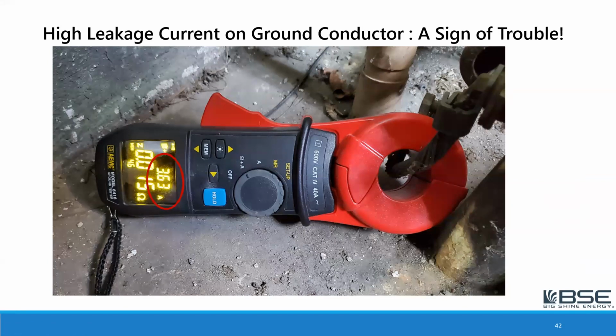And very often we find that inside a distribution panel, or even inside a specific piece of equipment, there's a connection where neutral and ground were connected where they shouldn't be. There are a few places in a building where the neutral and ground must be connected according to code, but everywhere else in the building, according to code, they must not be connected.